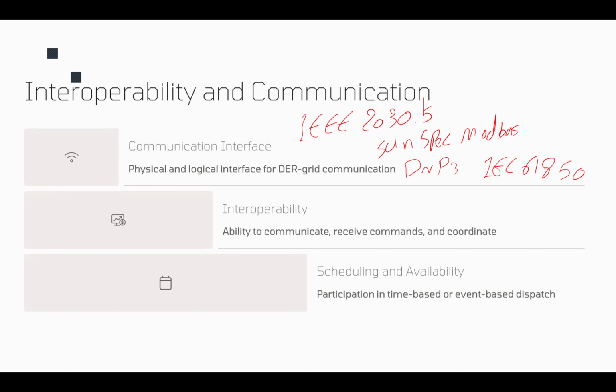Now, they also should have a scheduling and availability capability, which is basically support for time-based or event-based dispatches. Okay. Another option that we also mentioned briefly is firmware updates. So DERs should be capable of remote firmware updates, so if the grid requirements evolve, we can apply the new settings and make sure of long-term compliance with the standard.